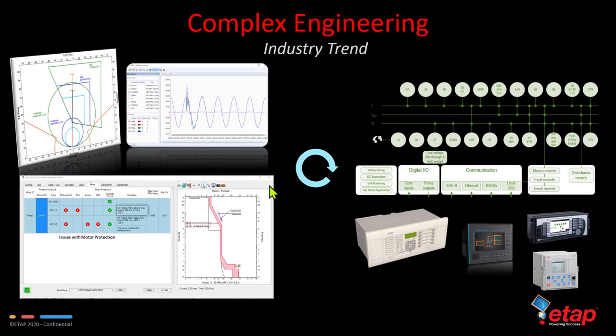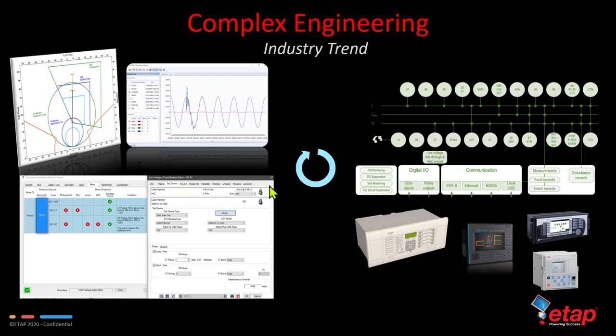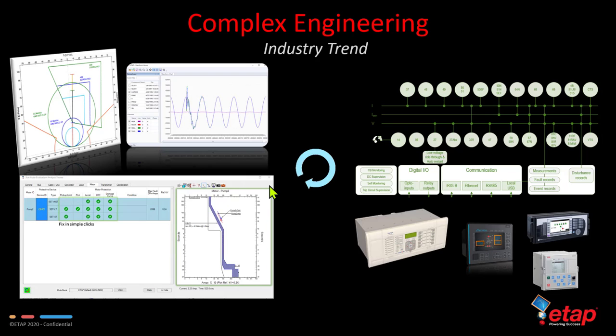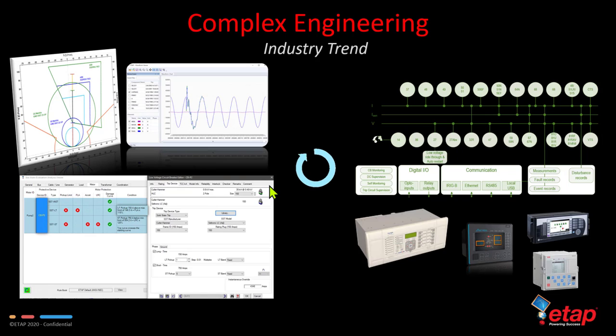Another industry trend is towards complex engineering. Protective relays offer a number of functions, including measurements, such as phasor measurements, events and disturbance records, fault recording, and other equipment supervision. It is possible to combine the digital twin model with power system analysis, coordination studies, automatic protection and coordination evaluation, arc flash assessment, historical events, real-time operating data, and so much more to constantly iterate and optimize the electrical system for any given condition. This leads to great flexibility in terms of operating the system, but it comes at the price of complex engineering.